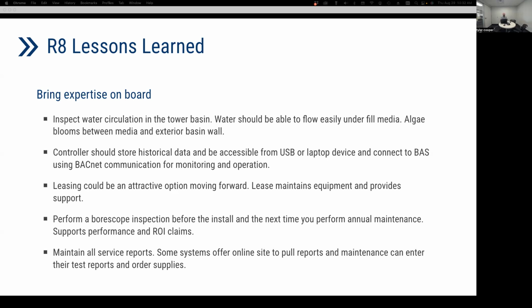Within that, one of the ways that we can verify performance for these systems is with a borescope inspection, just measuring the scale within the systems before and after these alternative water treatment technologies are installed. It really helps to verify that performance and support the ROI on those technologies. And last piece, maintaining all your service reports. Being able to go back, look at performance over time, and see how we're maintaining those really just demonstrates the performance of these systems and how they should be operating.